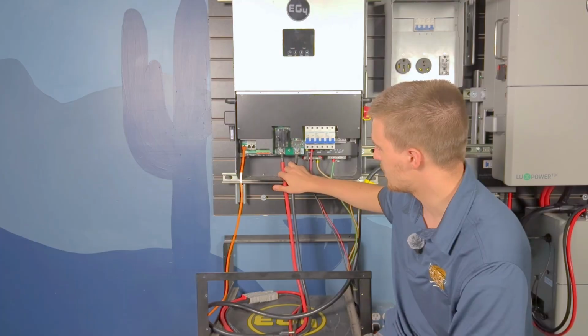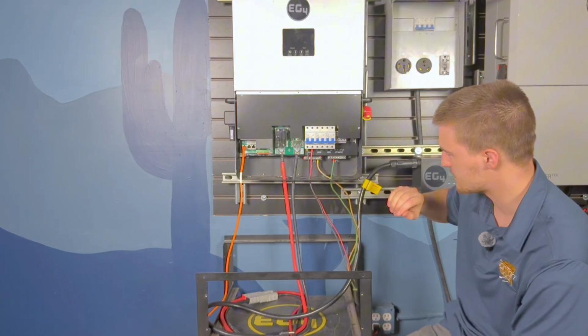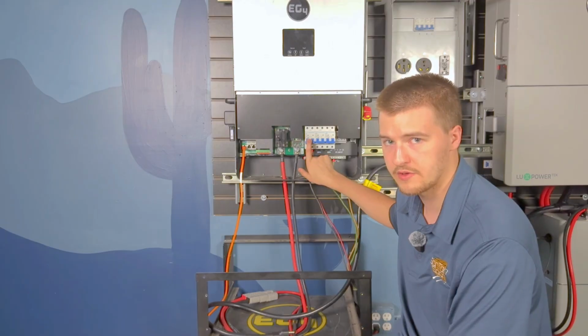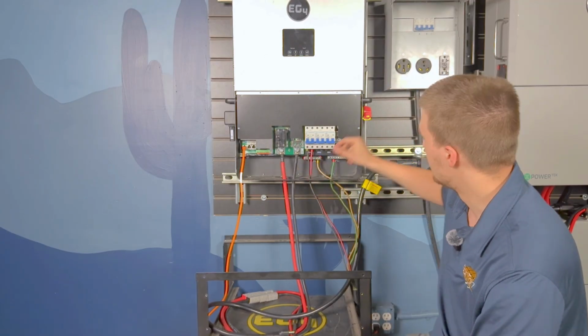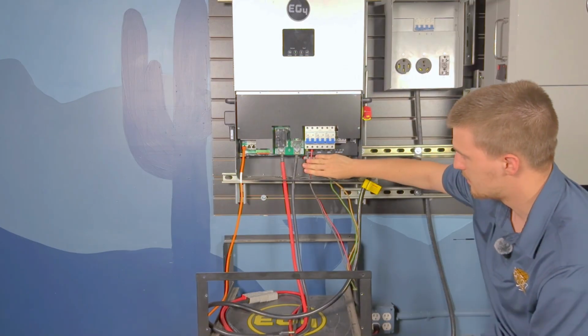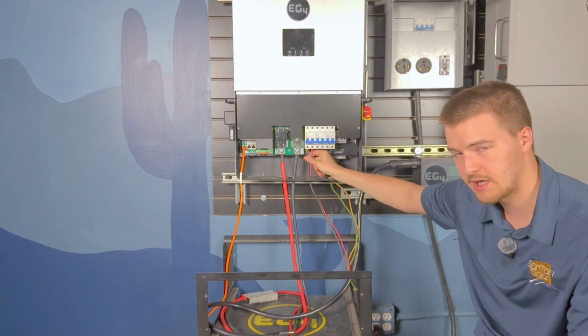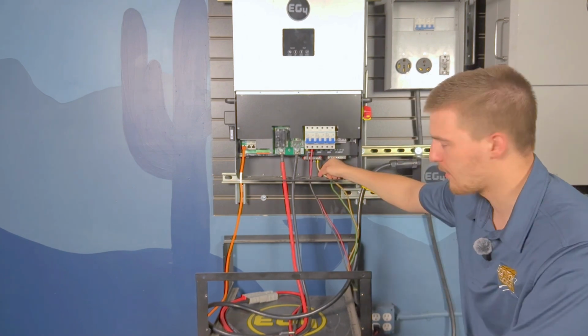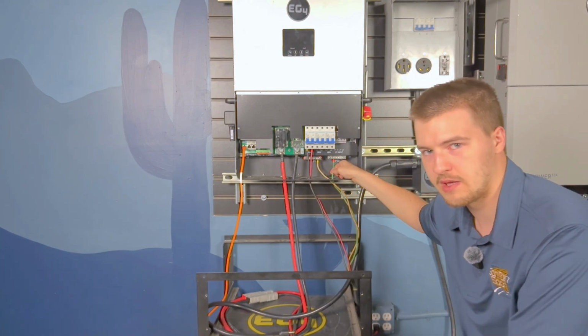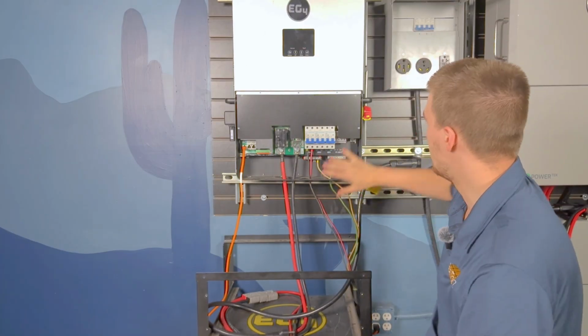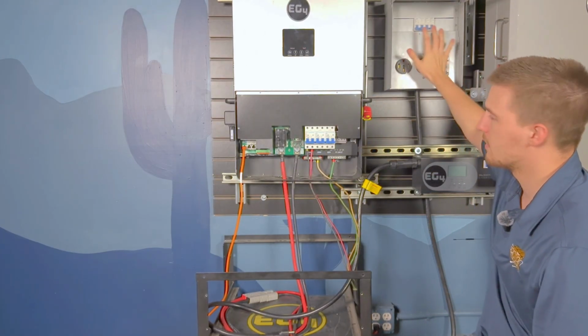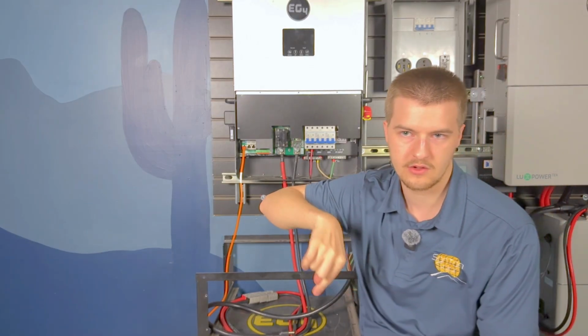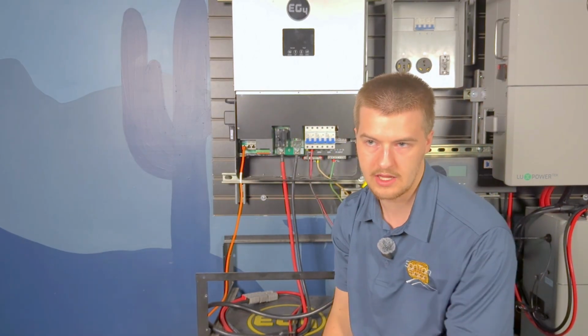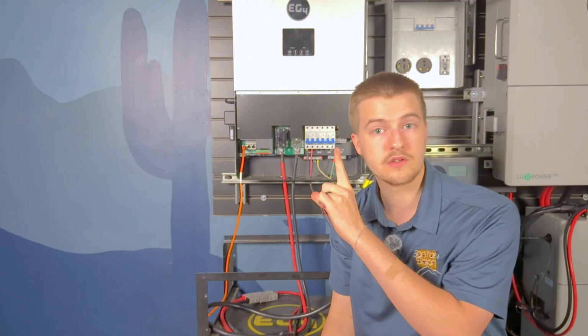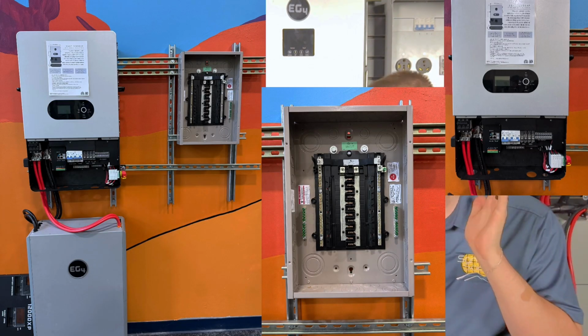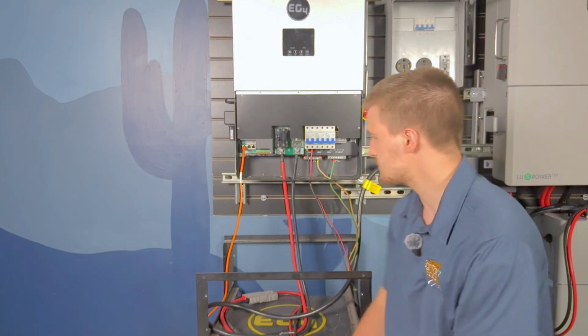When it comes to turning on these inverters or connecting them, specifically for an off-grid setup with our loads panel - this is my loads panel here, this is how I connect it. I always do black as L1, red as L2, white as my neutral, and green as my PE or physical earth. That all goes to your loads panel. This isn't what a normal loads panel looks like - if you're here in Arizona and want to see what a system looks like, we have a couple in our showroom, which I'll show on screen now. So that's how your loads panel would look.